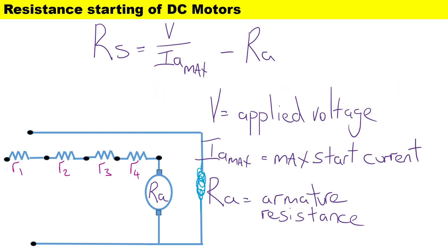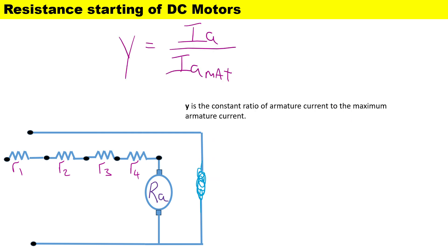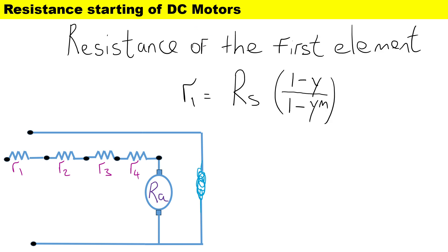To calculate the total starting resistance, it is V over Ia_max minus Ra. V is the applied voltage, Ia_max is the maximum starting current, and Ra is the armature resistance. Y is the constant ratio of the armature current to the maximum armature current.